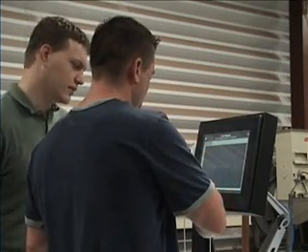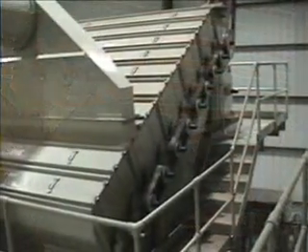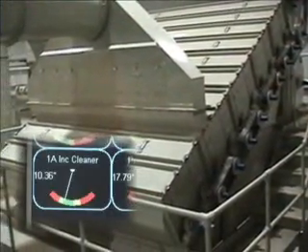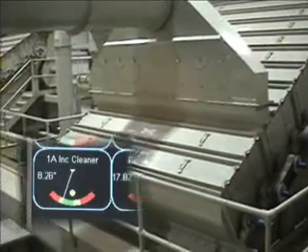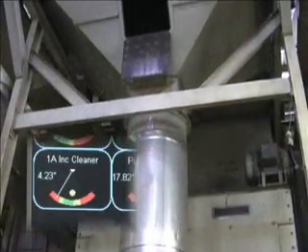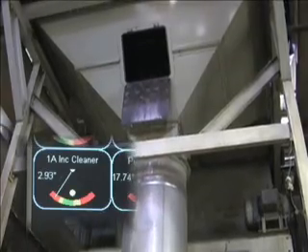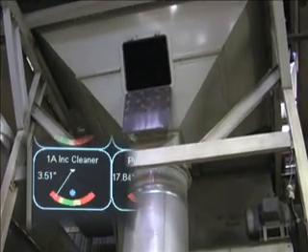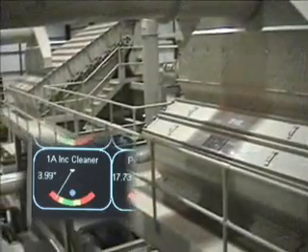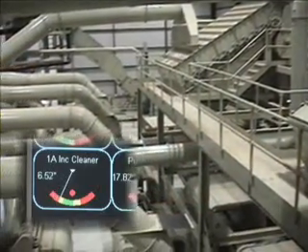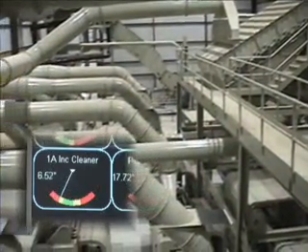Air Tools provides an easy window to observe just what is happening and calculate strategies to eliminate the resistance to flow. Inclined cleaners are a good candidate for Air Tools monitoring. Access doors are frequently left open, gaskets get torn, and structural leaks on older cleaners are common. Cold air leakage into inclined cleaners can waste drying fuel and hurt grade.